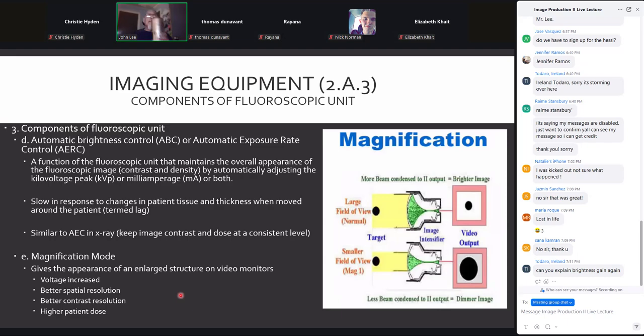Advantages for fluoroscopy included magnification, which we'll talk about in a second, but it did have a device that operated similarly to the automatic exposure control in static rad. The automatic brightness control or automatic exposure rate control was a device that could detect the amount of radiation coming through the patient into the system and adjust the KV, the MA, or both, depending on what kind of study it was, based on fluctuations in that exposure.